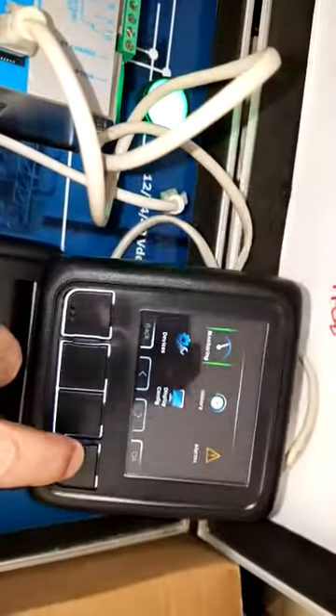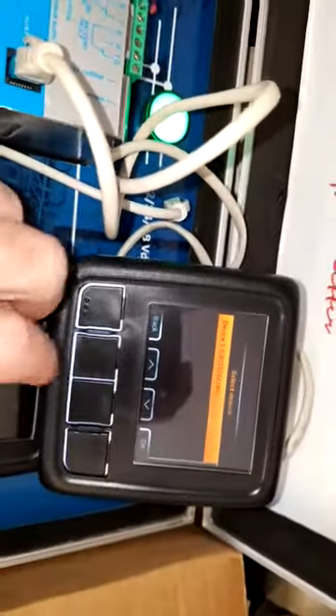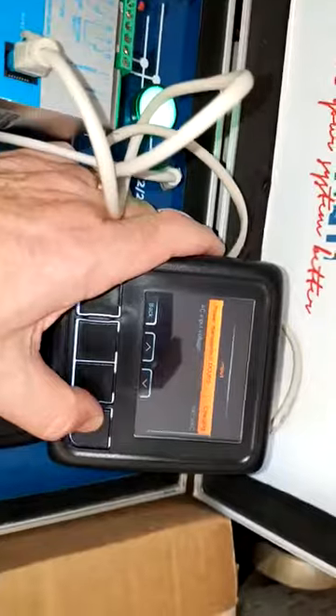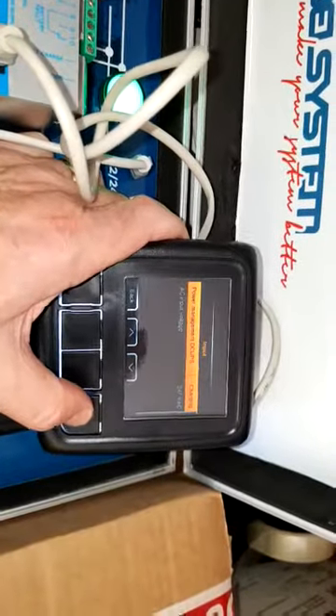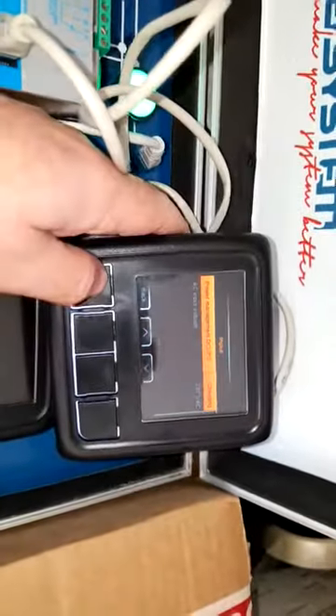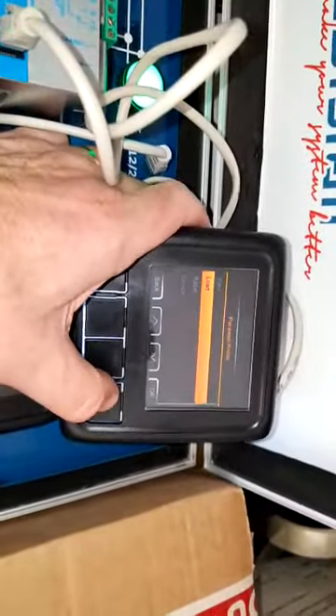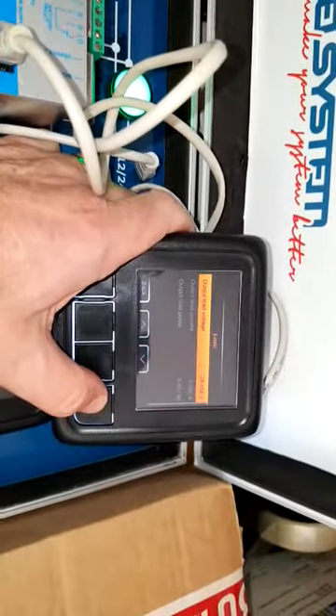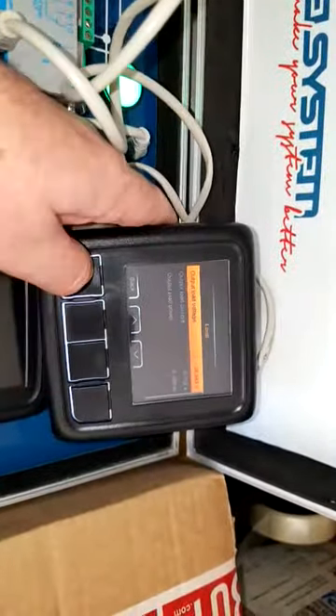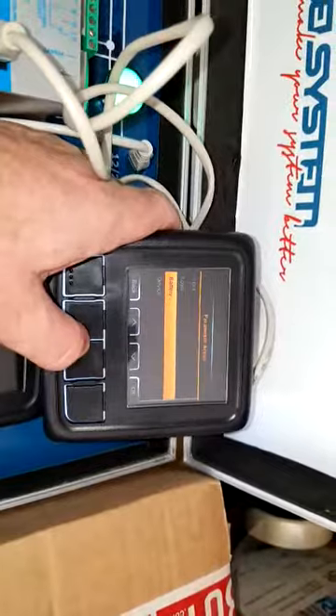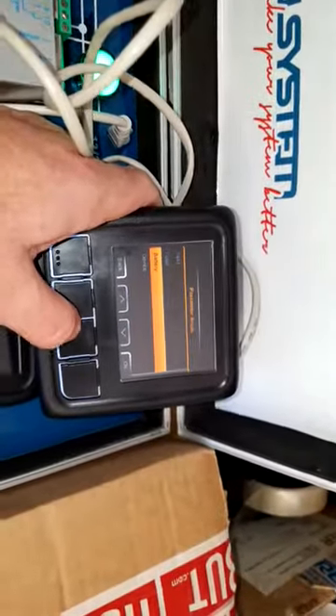You have the device, the monitoring. If you take a look at that, it shows you the devices and monitoring. You can add other devices to it, but from the monitoring you get the input, which will give you the actual voltage. But also you have power management of the DC UPS charging. It tells you what is going on. It tells you the load, the output voltage, the output current, and the output load power. There's very little power load on this. It's only a couple of LEDs on this display.